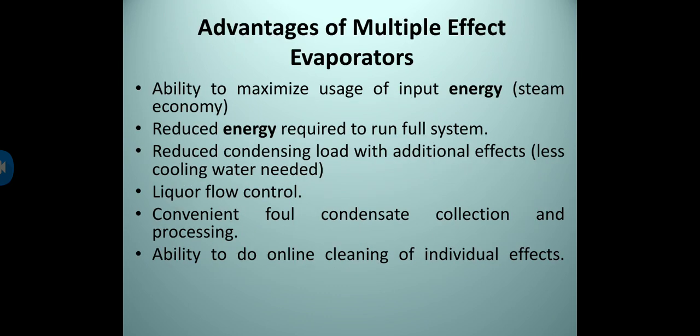Now see here the advantages of the multiple effect evaporator. The first advantage is the ability to maximize use of input energy, meaning steam economy. Next is reduced energy required to run the full system, then reduced condensing load with additional effects, that is, less cooling water needed. The next one is liquor flow control. Then convenient foul condensate collection and processing. Then the ability to do online cleaning of individual effects.